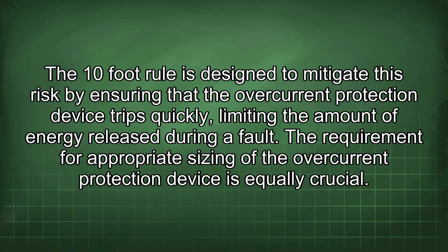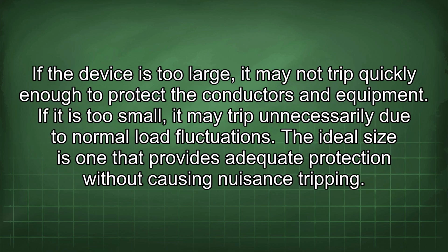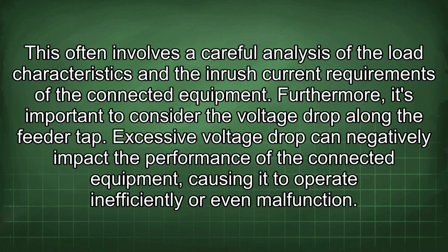The requirement for appropriate sizing of the overcurrent protection device is equally crucial. If the device is too large, it may not trip quickly enough to protect the conductors and equipment. If it is too small, it may trip unnecessarily due to normal load fluctuations. The ideal size is one that provides adequate protection without causing nuisance tripping. This often involves a careful analysis of the load characteristics and the inrush current requirements of the connected equipment.